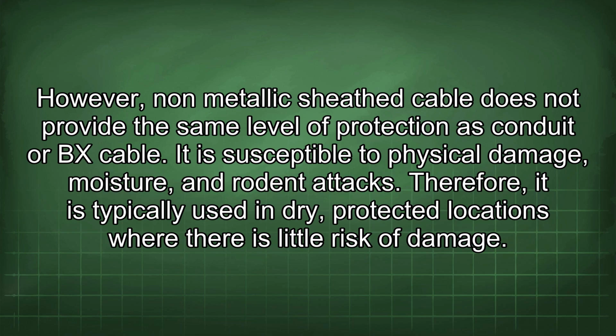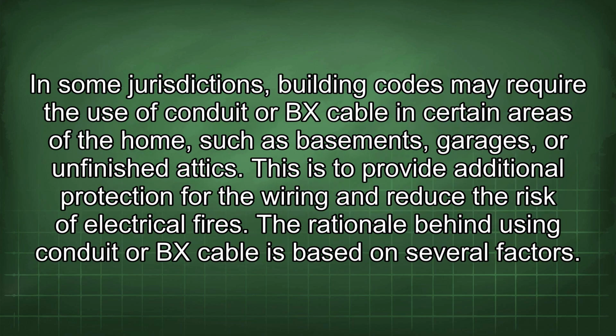However, non-metallic sheathed cable does not provide the same level of protection as conduit or BX cable. It is susceptible to physical damage, moisture, and rodent attacks. Therefore, it is typically used in dry, protected locations where there is little risk of damage. In some jurisdictions, building codes may require the use of conduit or BX cable in certain areas of the home, such as basements, garages, or unfinished attics. This is to provide additional protection for the wiring and reduce the risk of electrical fires.